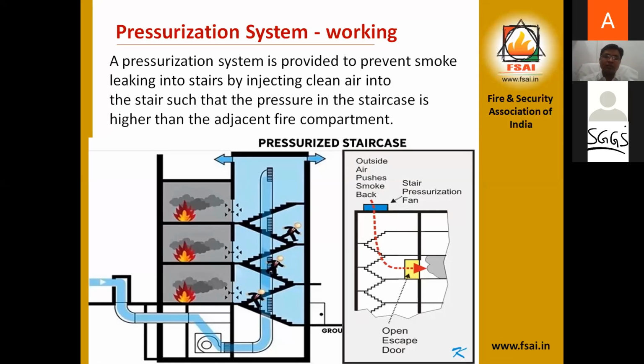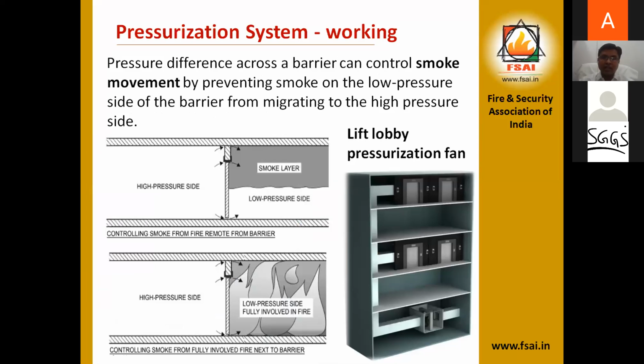Because the pressurization of the staircase is done from the bottom of the staircase, the pressure in the staircase is high while the pressure in the fire compartment is low. Because of that, the air pushes the smoke inside the compartment and it does not come out. In the second figure, you can see that the outside air pushes the smoke back. You can see the red arrow pushing the smoke inside the room and stopping it from spreading into the staircase. Pressure difference across the barrier can control smoke movement, preventing smoke on the low pressure side of the barrier from migrating to the higher pressure side.